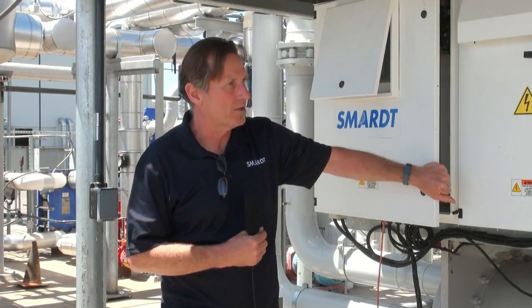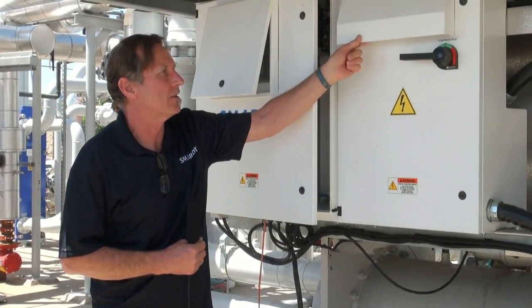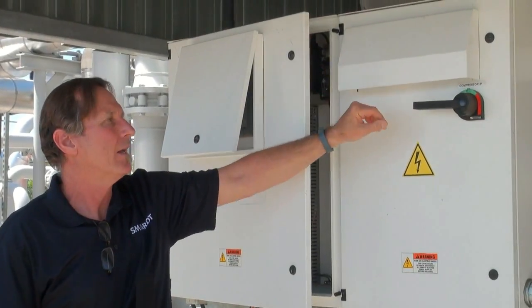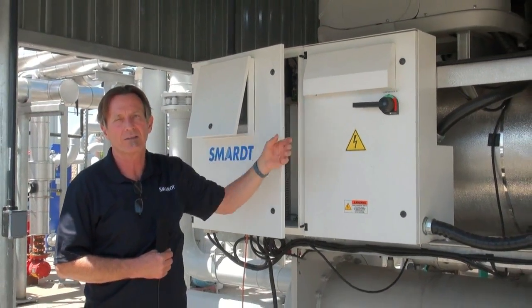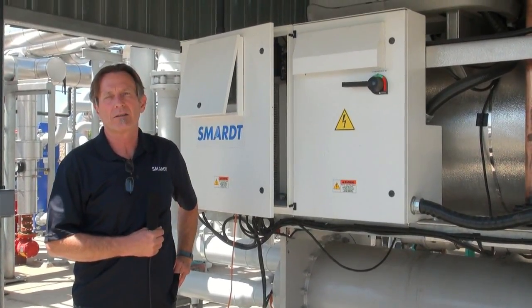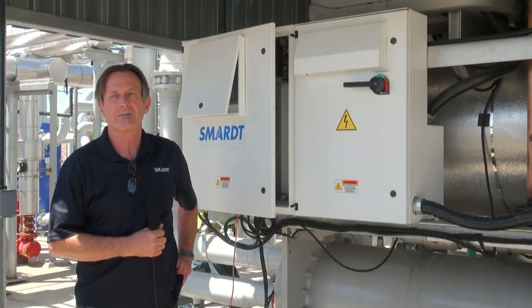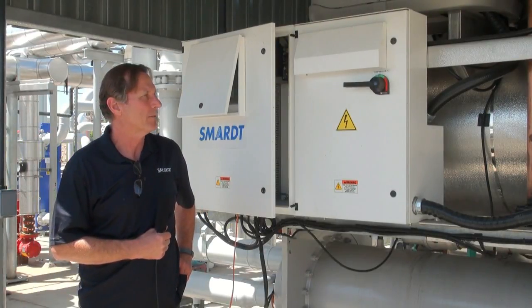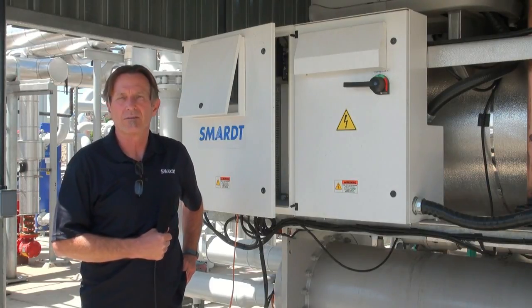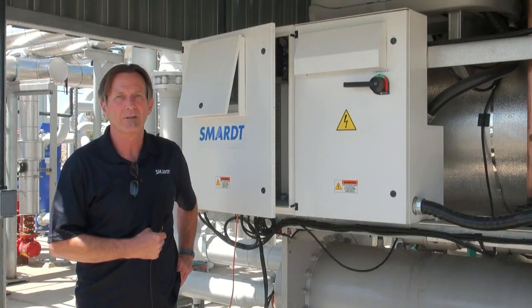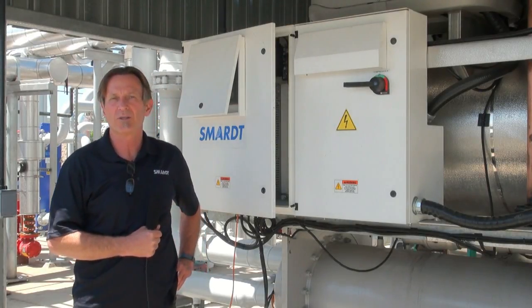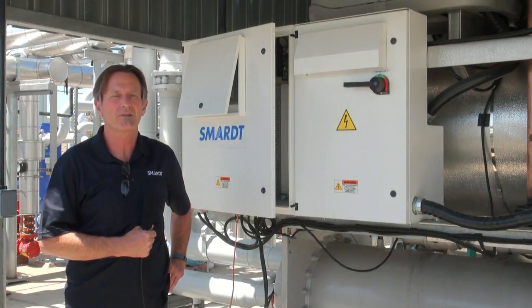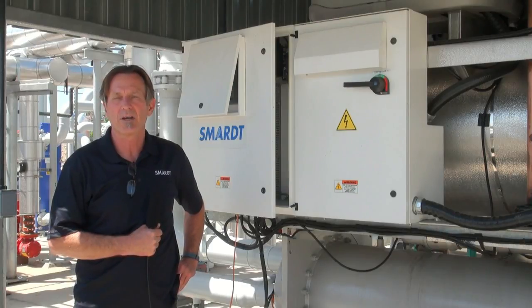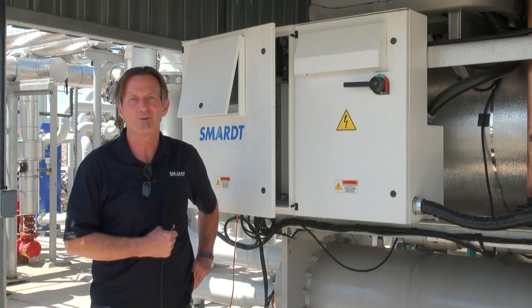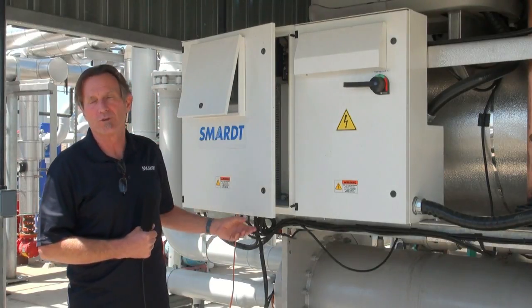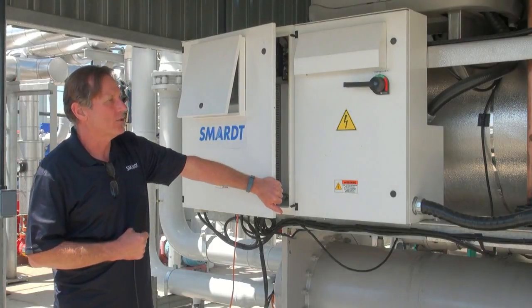On these doors, you see we've got a louvered panel. This is an eyebrow to keep the weather out, but you've got louvers underneath here with a filter behind there. That's the filter that you'd want to periodically change out or clean. The more often you change that filter, the less dirt you'll find in the cabinet itself. But probably once a year when you do your annual, I'd certainly go inside that cabinet and clean it out. Make sure it's not accumulating too much dust, especially if you get a little dirt, little dust, and some moisture. Then you could have some issues with blowing fuses or having issues electrically. Nuisance problems, basically. So to each compressor you have a disconnect switch.